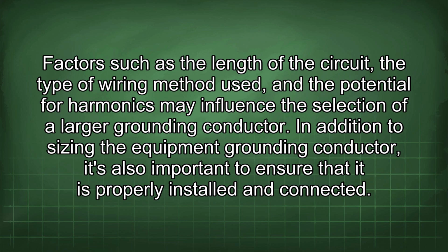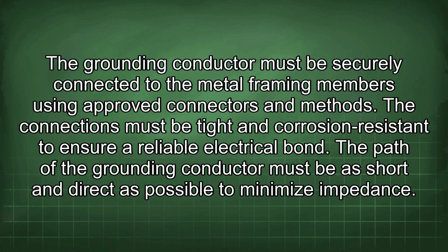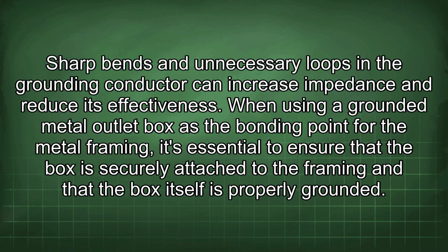In addition to sizing the equipment grounding conductor, it's also important to ensure that it is properly installed and connected. The grounding conductor must be securely connected to the metal framing members using approved connectors and methods. The connections must be tight and corrosion resistant to ensure a reliable electrical bond. The path of the grounding conductor must be as short and direct as possible to minimize impedance. Sharp bends and unnecessary loops in the grounding conductor can increase impedance and reduce its effectiveness.